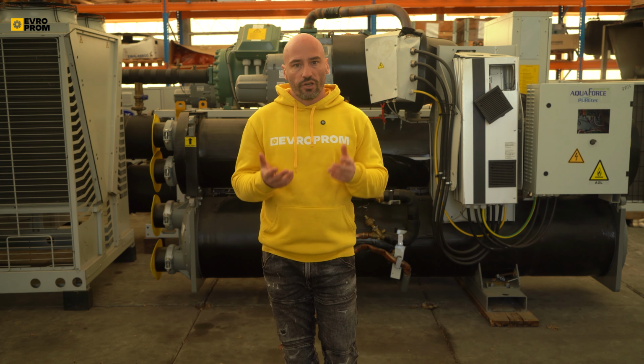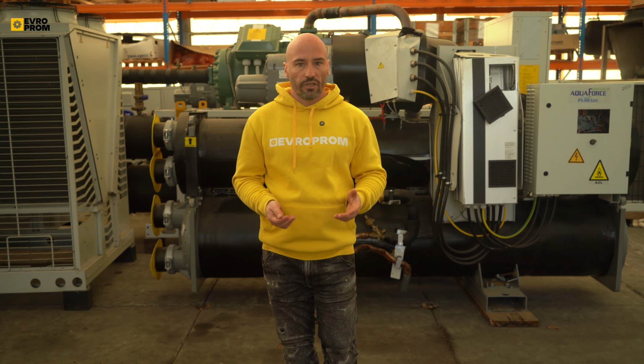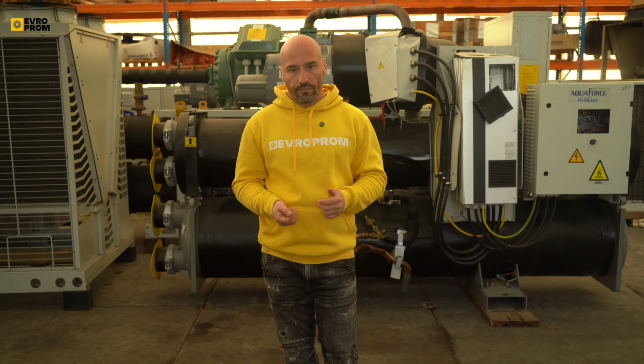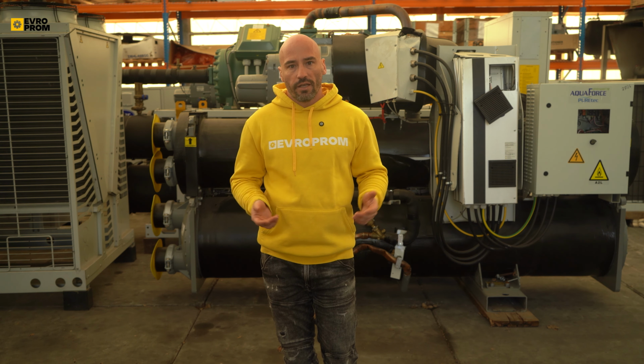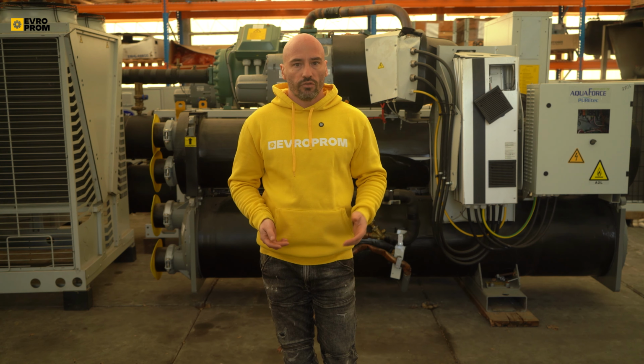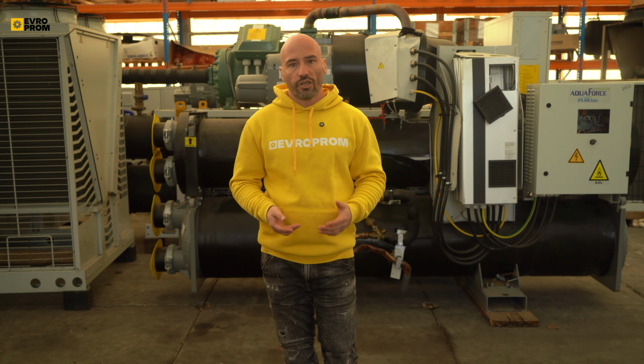Each type of refrigerant has its own pressure specification at a given outdoor temperature, so if the parameters match, that's a good sign. If not, unscrew the cap on a refrigeration line nipple and try to give a quick spray to see if there is any pressure in the system at all. Be extremely careful when doing this. If there is liquid refrigerant, it can spray into your eyes under high pressure.